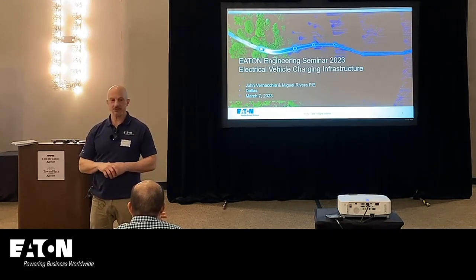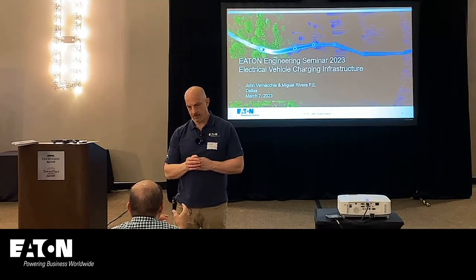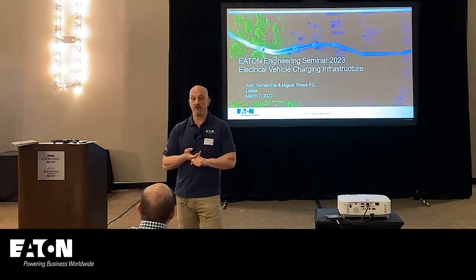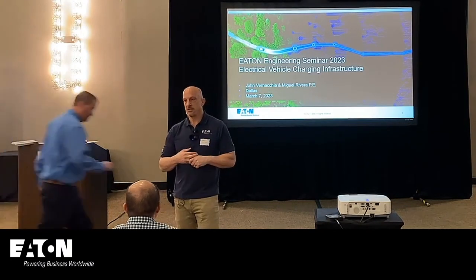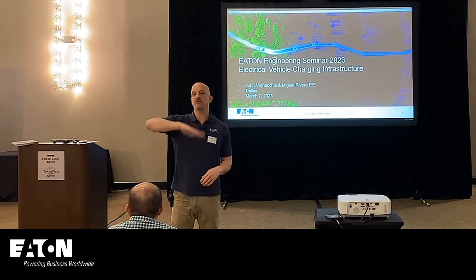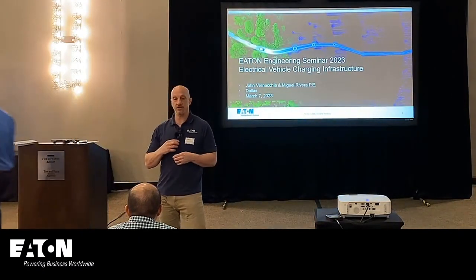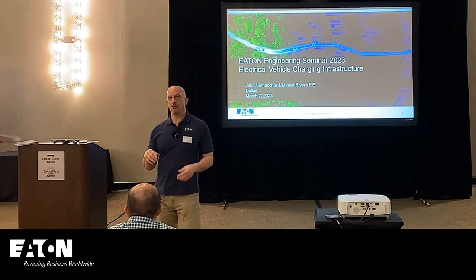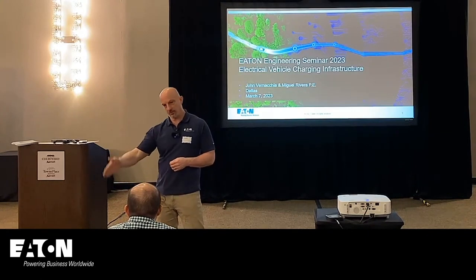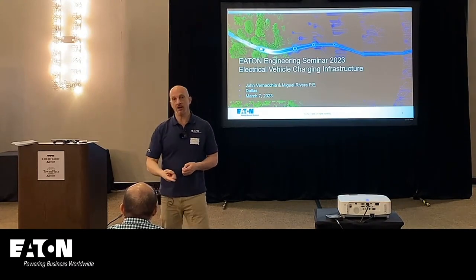So if I want to improve the power factor for the system, and I add capacitors, I need to watch out for what? Yeah, if you're adding capacitors when you have harmonic sources. The Tacoma Narrows Bridge failed because the wind was blowing, but if the wind didn't blow, the bridge would have been fine. What happened was the bridge started to move. So if you don't have harmonic currents, then the current distortion wouldn't get amplified. You can have a resonant point when you put a capacitor on, but when you excite that resonance at the frequency of interest, which is what harmonics are, 300 hertz, 420 hertz, whereas before you only had 60 hertz, the resonant point was over there somewhere. Now you have this resonant point. We have a couple good videos on that one as well.